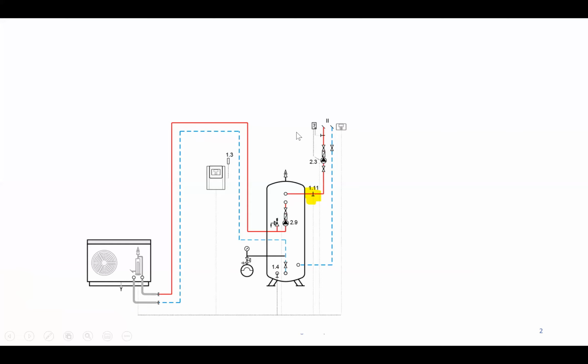If we've just got a standard single heat pump installation with a WPM and a single heating circuit - now this probably suits more than 50% of the installations we're seeing. Obviously we do a lot of cascaded jobs with multiple heating circuits, but in the case of just one heating circuit, it goes to a buffer tank, and the WPM, if so chosen, can effectively just manage the buffer tank.